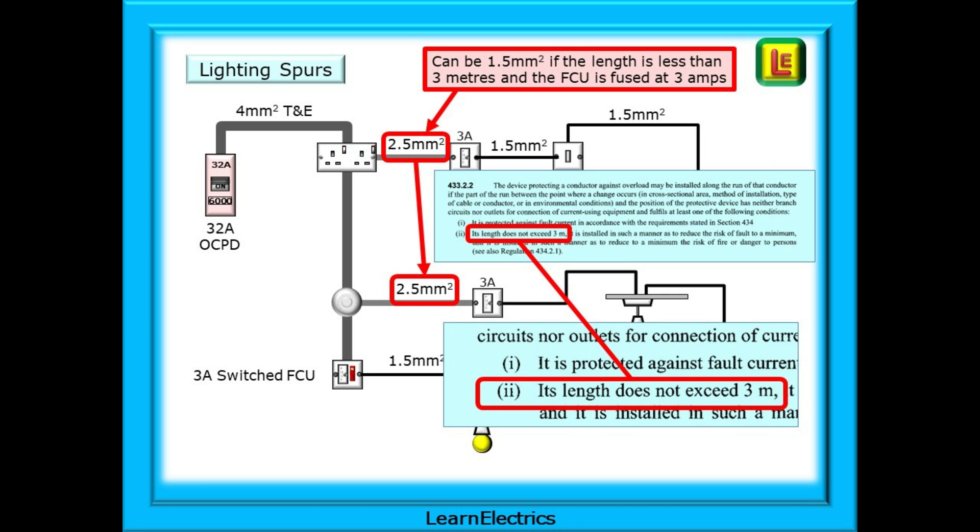Let's go back to the lighting spur that comes off the socket and the lighting spur taken from the junction box. We have 4-square-millimeter cable on the radial trunk, 2.5 between the socket and the FCU, and then 1.5 after the FCU. Three different sizes of cable. This is because the cable should always be an appropriate size at each point on the circuit. Except that there is a regulation that allows us a little leeway. Regulation 433.2.2 tells us that if the 2.5-square-millimeter cable going from the socket to the FCU is less than 3 meters in length, then it can be just 1.5-square-millimeter in size. But there must be no branches in the cable and no outlets of any kind. Just a simple piece of cable from the socket or junction box to the 3-amp FCU and not more than 3 meters in length.